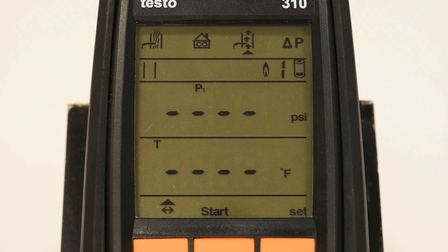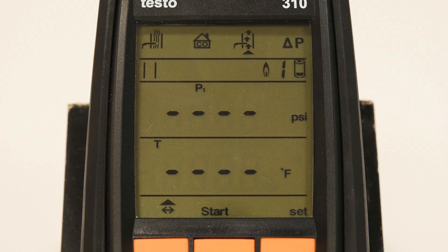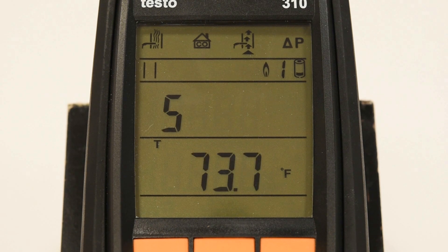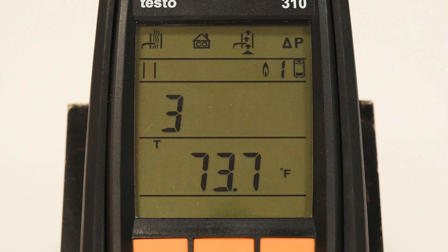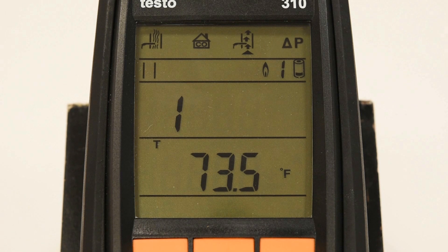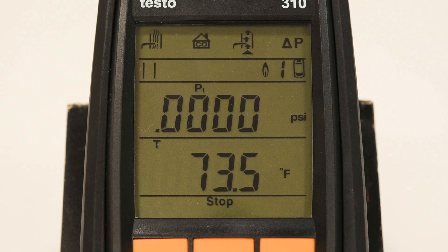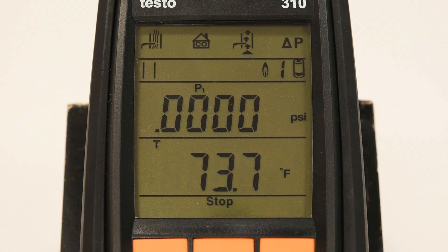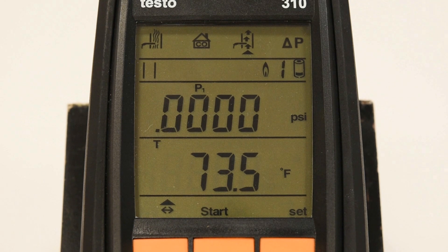When selecting draft measurement, it is important to start the test with your flue gas probe outside of the flue. You can then start the measurement using the center orange button and a draft zeroing countdown will appear on screen. Make sure that the probe remains still during this countdown to achieve a proper zeroing. You can stop the measurement by pressing the center orange button again.